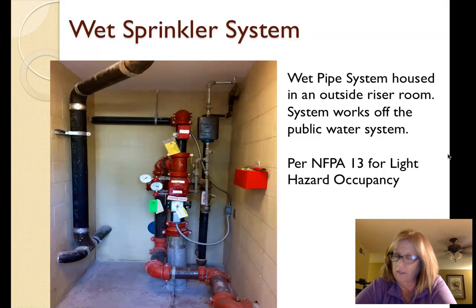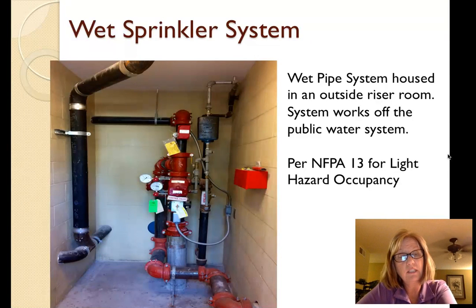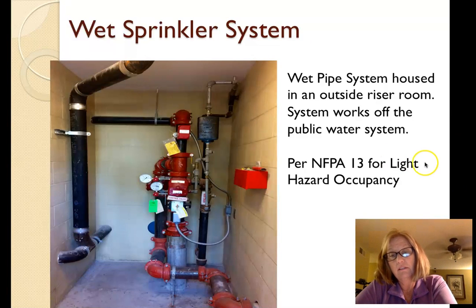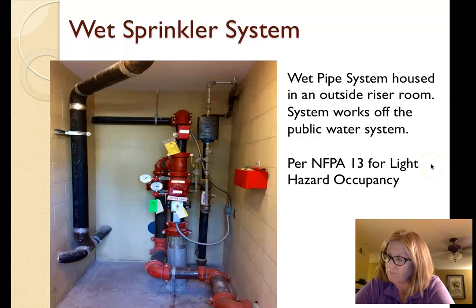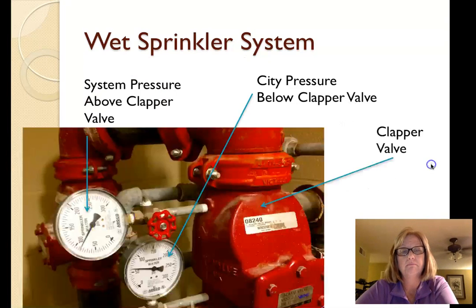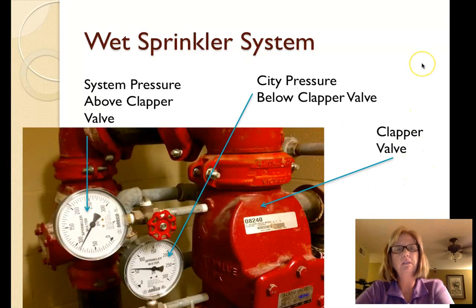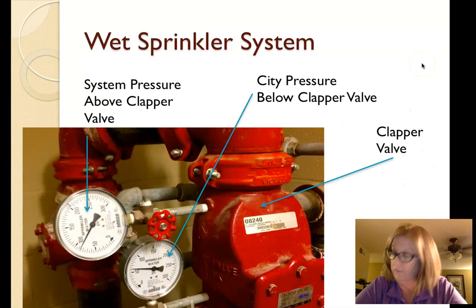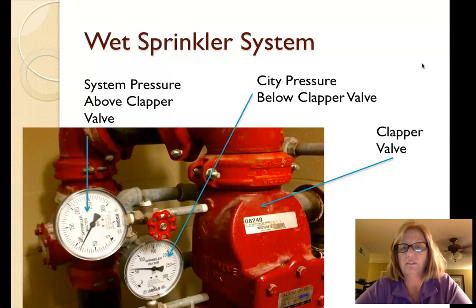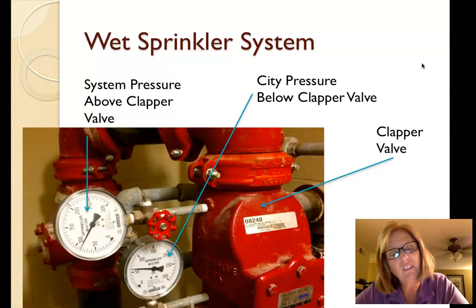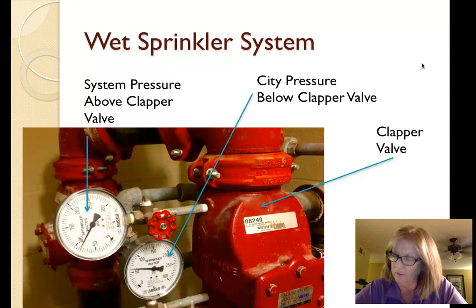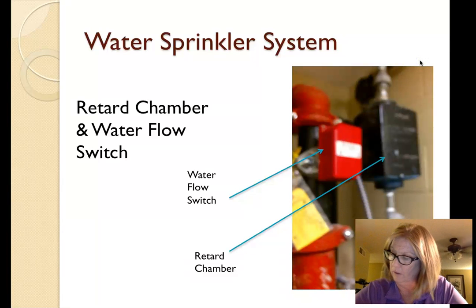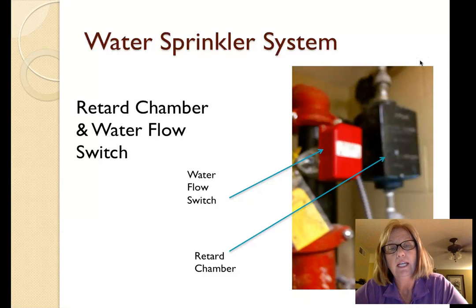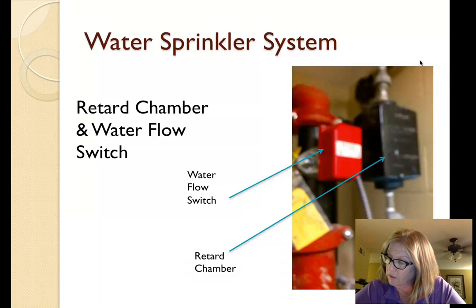Inspector Ellsworth said that this is because the inspection team wants to see the inspections completed annually in the system, that the system has no issues. The city pressure was at 55 psi below the clapper valve, and the system pressure was at about 75 psi above the clapper valve. He pointed out to me the retard chamber and the water flow switch and some other features in the riser room, including the gong.